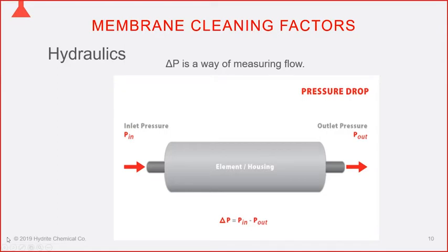Be careful if using chlorine to treat COW water — if you use that water to clean ROs or nanos, you may have to dechlorinate it first. Every account manager with membranes in their territory should know how to calculate the hydraulics of their system using that pressure drop equation and review it periodically. If the hydraulics are good and the chemistry is good, the system should run error-free for a long time unless there's a mechanical failure.